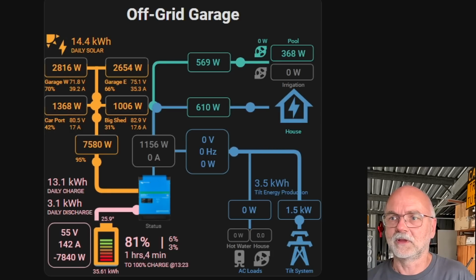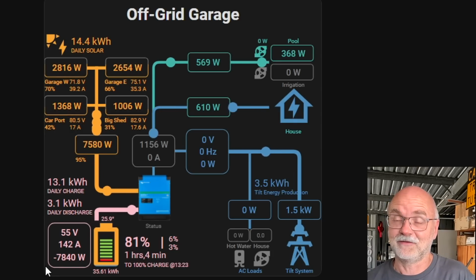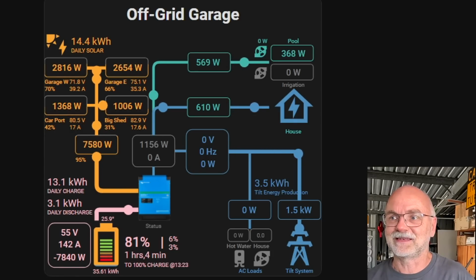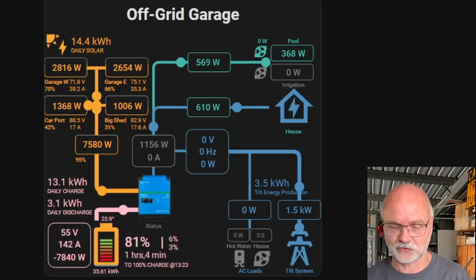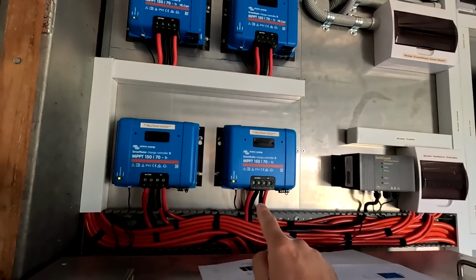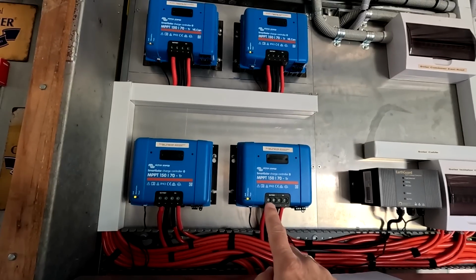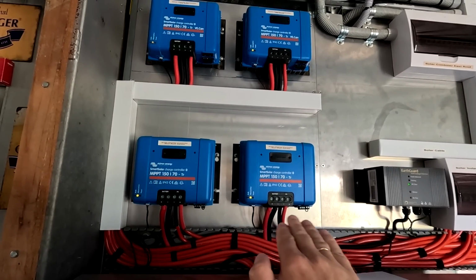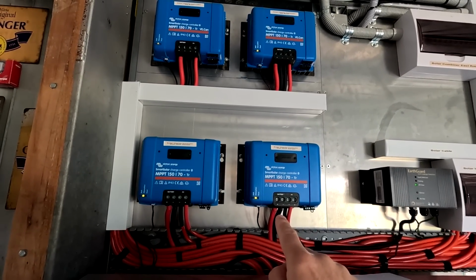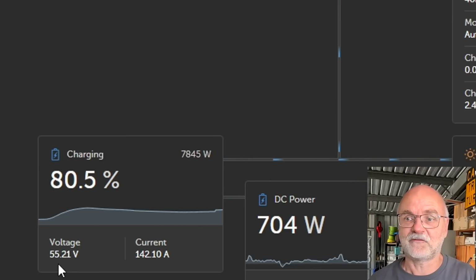All right, so we are now at 7.8 kilowatt, 140 amps into the battery, okay. But now everything is controlled via the solar charge controllers. And interestingly, we can also see that all MPPTs have now switched to absorption mode, from bulk to absorption. So they're keeping the voltage now constant at 55.2 volts. We have actually reached the absorption voltage of 55.2 volts. Yep, we are at 55.2 volts.